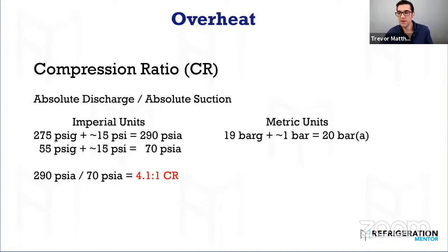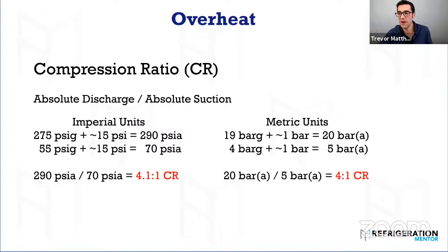Let's do it in metric. If you have 19 bar plus approximately 1 bar, that's 20 bar A over, say, 4 bar suction plus 1 bar is 5. So now you've got a 4-to-1 compression ratio. You're okay, depending on the compressor, and that's usually what you're going to see in medium temp applications. Low temp is going to be a lot higher. But you do need to understand this, because if you have a dirty condenser and an increase in pressure, it's plugged up, say you get a 25 psi increase. Your compression ratio may go up 1 or 2. So instead of 4-to-1, it might be 5-to-1, we'll say.